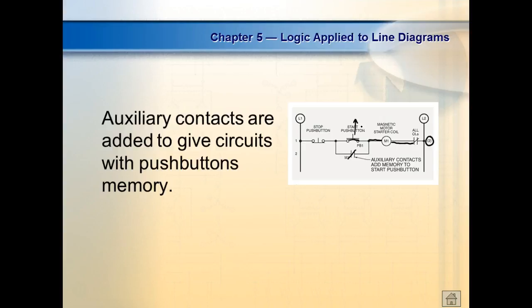So if I had a switch out here and I had a motor running and I flipped that motor on, your power failed, the motor would stop. When power comes back on, what will the motor do? It'll take off, right? No matter if I'm out there looking at it or working. If the power fails, we lose L1, L2, this guy here drops out. Now when power comes back on, the operator has got to deliberately do what? Push the start button. So this is why most companies use this memory circuit to run motors. So that way if power fails, when the power comes back on, that motor's not going to take off.